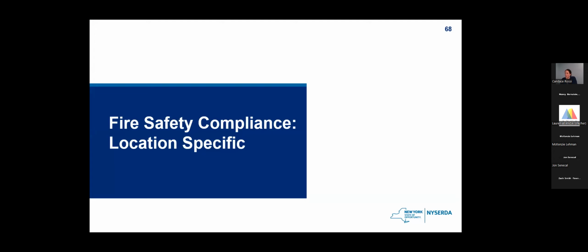All right, so to review, we've now gone over the requirements that all commercial and utility installations will need to meet, as well as additional requirements based on system chemistry. So now lastly, we'll go over the different requirements needed based on where the system is located. So this is something that was cool in the 2021 draft codes that we adopted in New York State. The 2015 codes really just looked at battery storage as kind of the same thing. The 2018 code looked at, not all batteries are created equal. There's different requirements for different electrochemicals. And in the 2021 code, they took it a step further: it's not just the type of battery, but also where the battery is located that could have different safety requirements. Basically, if it's going to be close to humans' health, or remotely placed. So yeah, now we'll go over those different requirements.